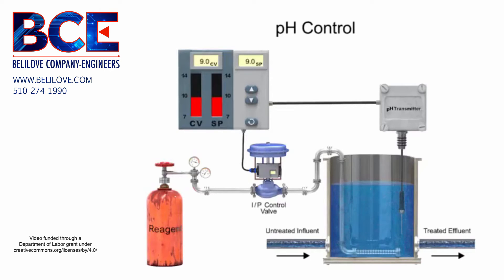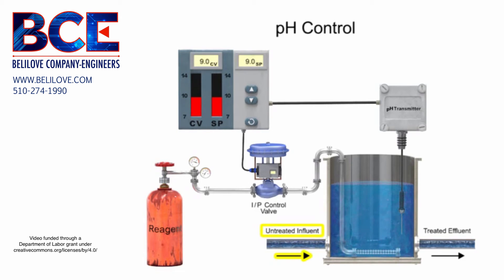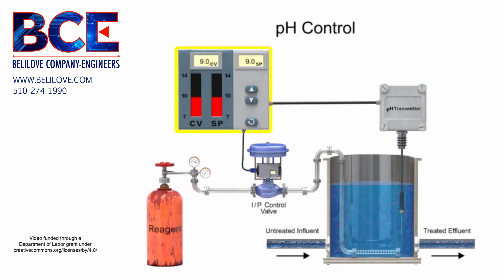An example of an automatic pH level control system is a water treatment process where lime-softened water is maintained at a pH of 9 using carbon dioxide as a reagent. As the untreated water or influent enters the tank, the pH is continuously monitored by the pH sensor. The sensor is the feedback device to the controller where the setpoint is compared to the control value.